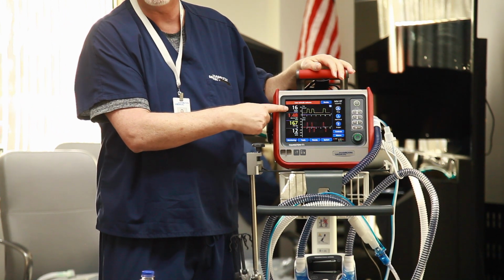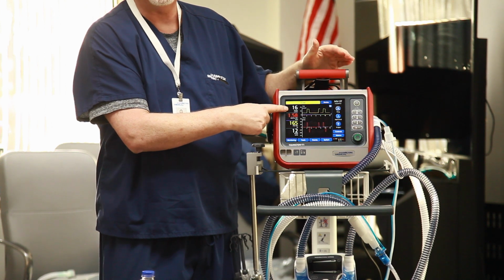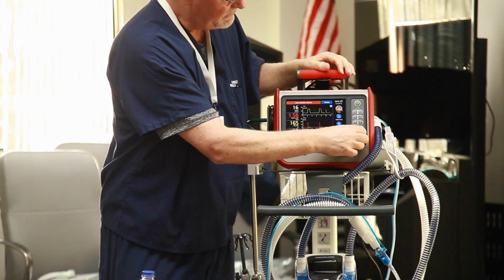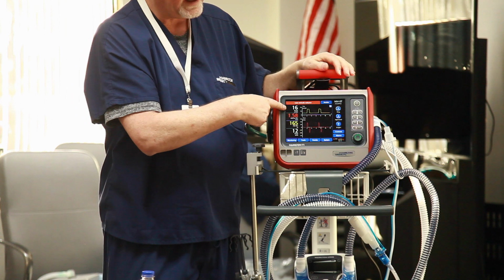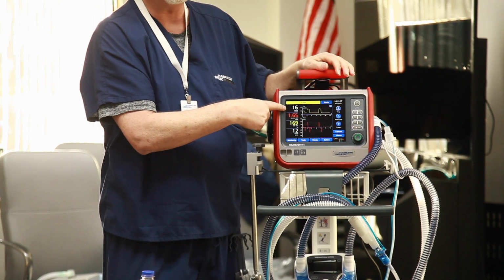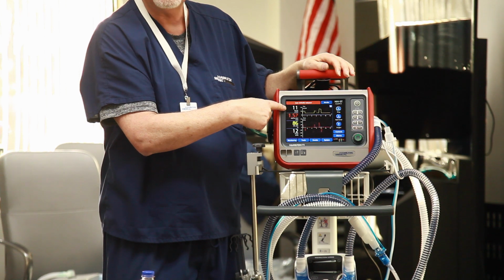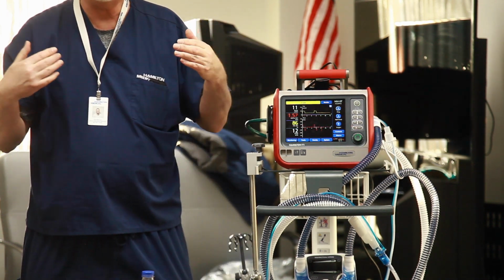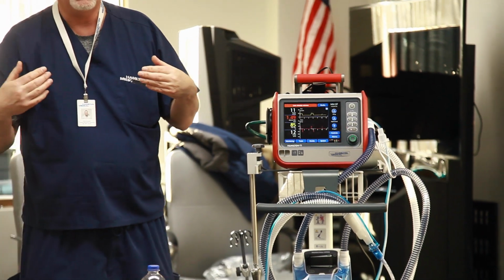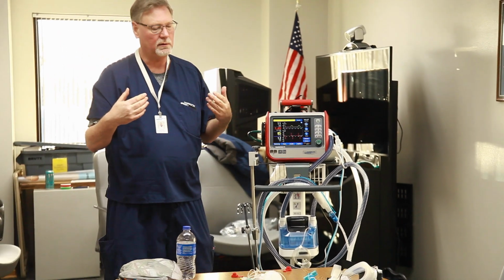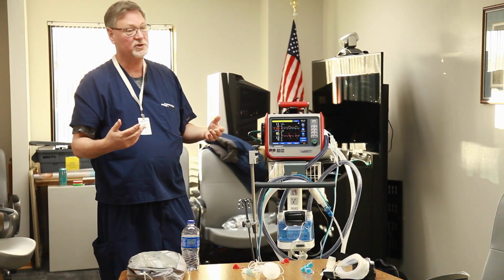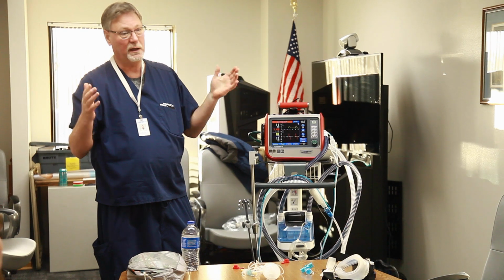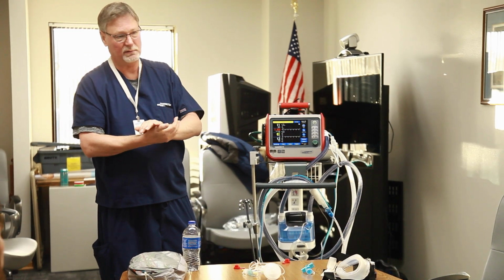Now you're going to look at your peak pressure and it's going to read like 16 or 17 or something like that. So you're going to say, that's not what you ordered. You wanted a total pressure of 10, correct? Yeah, 5 plus an inspiratory pressure of 5 to get me 10, 11, whatever is going to pop up here, okay? I know, we have to change our brains a little bit. I don't like to change my mind. You're changing a lot here, but you're going to be okay. It's not going to be too bad.